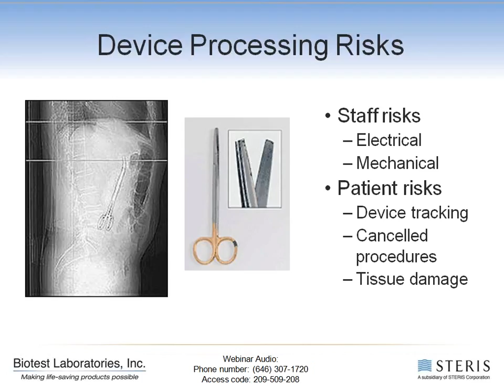There are also risks to the staff, as I said, on electrical and mechanical concerns, in particular for shocks that can pose an infection risk, and for patients where inadequate reprocessing can lead to canceled procedures and tissue damage. For example, here you have an example of a device that not only has lost a sharp edge, but obviously two of the tips have actually broken off. And of course, when that is handed to a surgeon at the wrong time in the wrong place, that can have quite a significant implication. These are some other examples of material compatibility concerns, which we will talk about a little bit later. But you will see examples here of adhesives breaking down, parts of devices being compromised due to the development of rust, and loss of color sometimes, which can lead to a lot of confusion surgically.